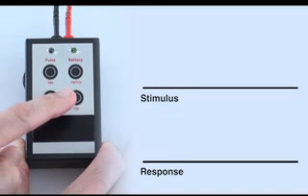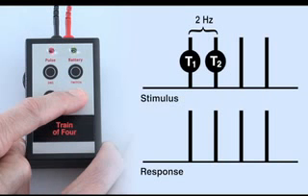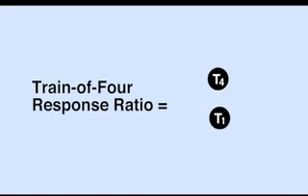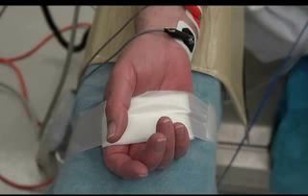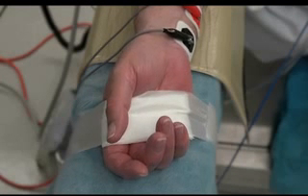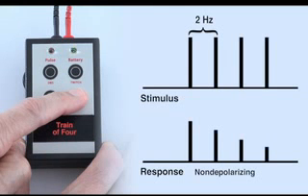The train of four pattern consists of four sequential single twitch stimuli — T1, T2, T3, and T4 — delivered at a frequency of 2 Hz. The train of four response ratio is calculated by dividing the T4 response amplitude by the T1 response amplitude. Calculate the train of four ratio before administering muscle relaxants and use it as the control ratio; the ratio should be 1 or 100%. During a partial non-depolarizing block, the ratio decreases or fades as the block increases.